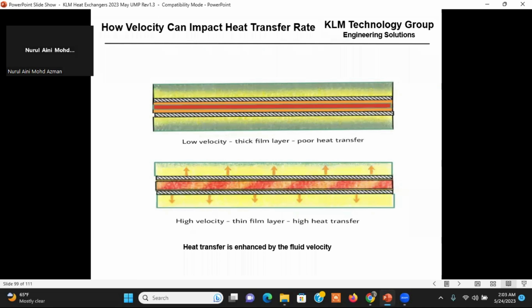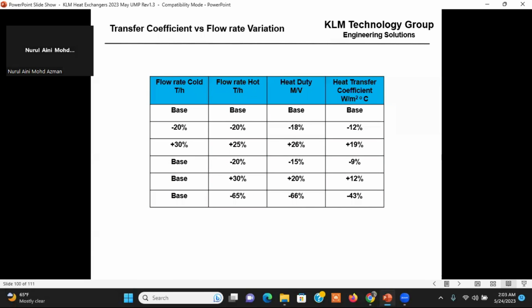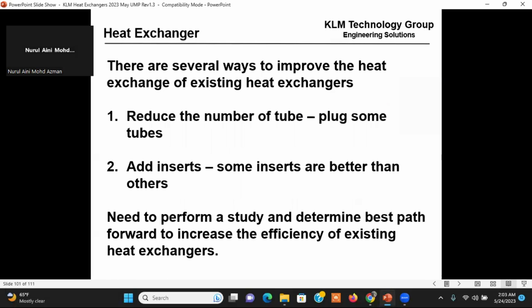If I know the plant's not going to run 110, 115%, I better design the heat exchanger for lower velocities. All right. And so if I have less flow, I can have 18% less heat duty and 12% less heat transfer coefficient. That makes sense to you. You can understand, if I break into that laminar flow, it's just going to fall off like you can't believe. Now, there are certain things you can do. You can run flow regimes. You can calculate the Reynolds number. And sometimes I've gone out and plugged some of the tubes. Okay, they way over-designed the heat exchanger. And I might plug 5 to 10% of the tubes, and the heat exchange actually goes up because the velocity goes up.